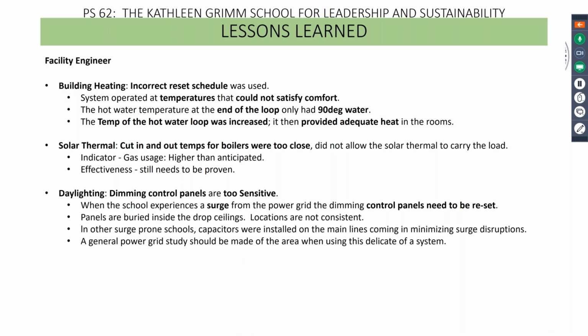For the facility engineer, they were having a lot of issues with the solar thermal system. Part of it was the initial testing, the contractor ran water through it, so we had to fix those issues. It was also oversized for what they thought our load was going to be. What we're finding in New York City is that we typically don't use anywhere near as much domestic hot water as the ASHRAE standards suggest, based on type and square footage. The design was based on ASHRAE sizing, so we had two 650-gallon storage tanks in this school for a maximum of 600 students, and that 1,300-gallon capacity ended up causing a lot of problems. The water just wasn't circulating through fast enough.